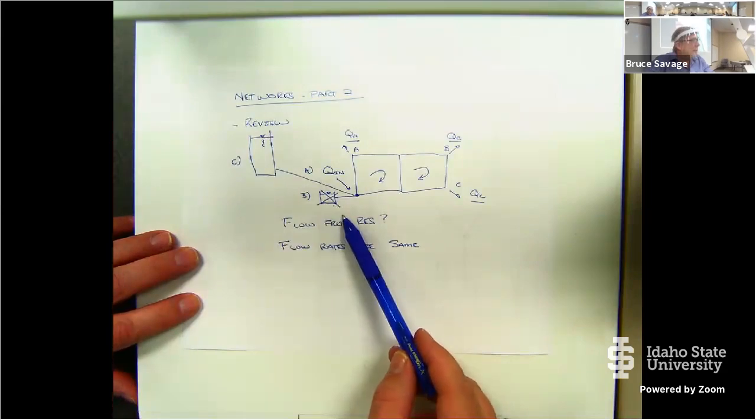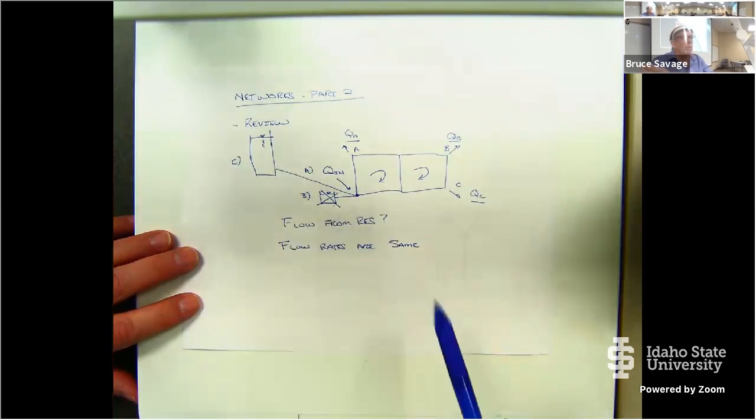For the flow rates, we've said nothing about solving for the pressures in the system. And at some point, we're going to want to know the pressures. So after we know the flow rates, can we solve for the pressures? Sure, we have to start at some known pressure, and then we just walk around our hydraulic grade lines, and we know the pressures everywhere after that. So we still have a second set of equations that we need to solve, but it's just plug and chug.